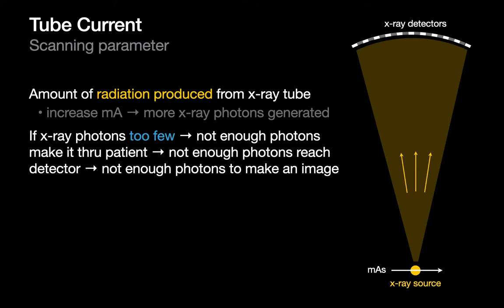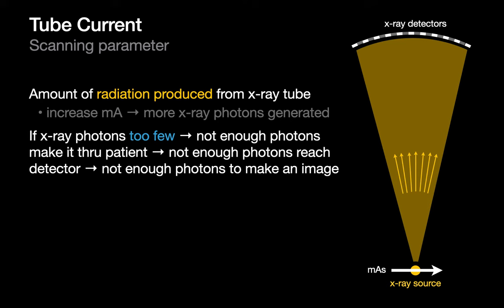X-ray tube current, expressed in milliamps (MA), influences the number of x-ray photons coming out of the tube. The more tube current, the more x-ray photons we shoot at the patient. It's important to shoot enough photons; if not enough reach the detector, we can't create an image. However, if we shoot too many, we'll create a picture but possibly give the patient an unhealthily high amount of radiation exposure.